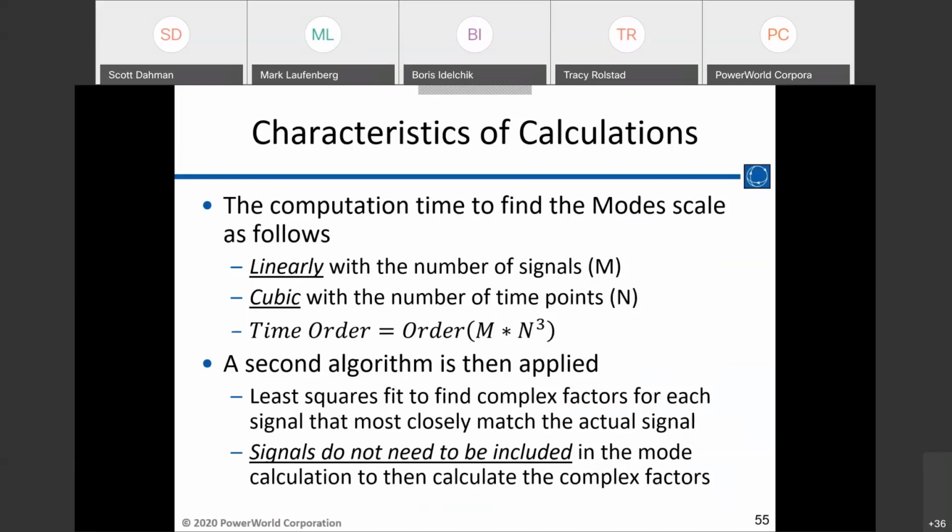When I say sampling, you're like, well, we sample at a quarter cycle because that's what we're running our simulations at. But a quarter cycle would be 1 every 240th of a second. That means we'd be sampling at 240 hertz, so we'd be able to pick up 120 hertz oscillations. But we don't even care about those. So why would we sample that much? In the algorithms for finding modes, we're going to do much, much lower than that.